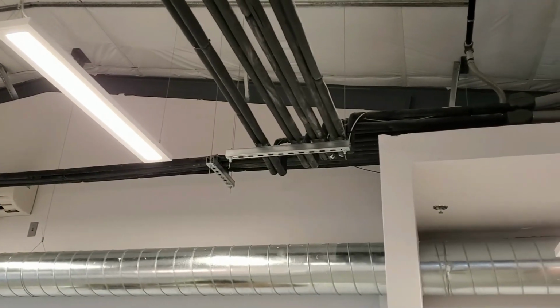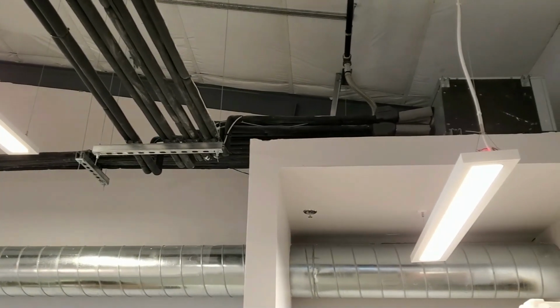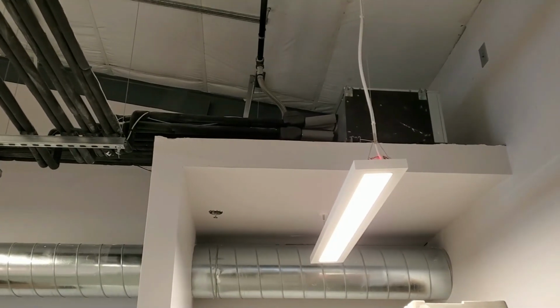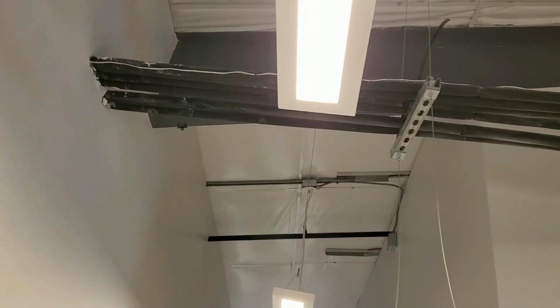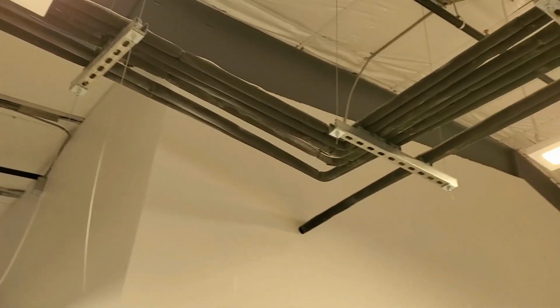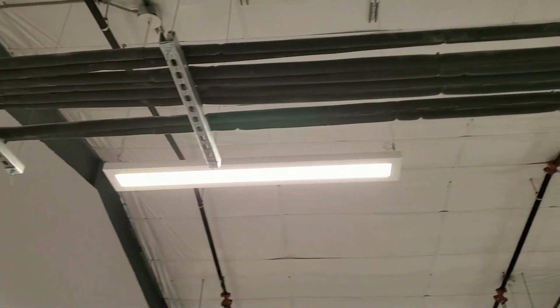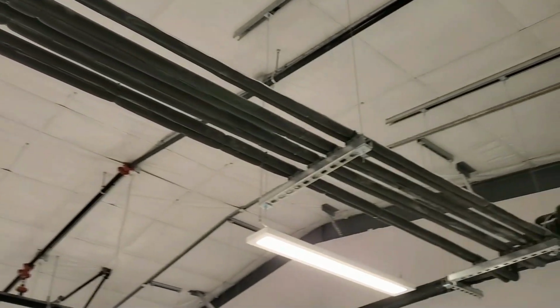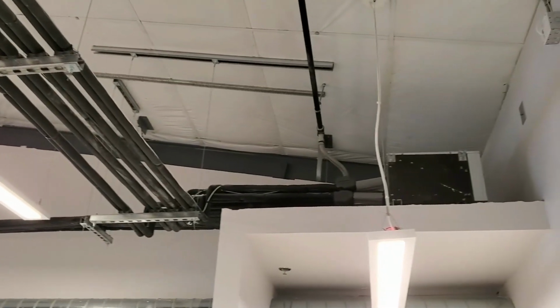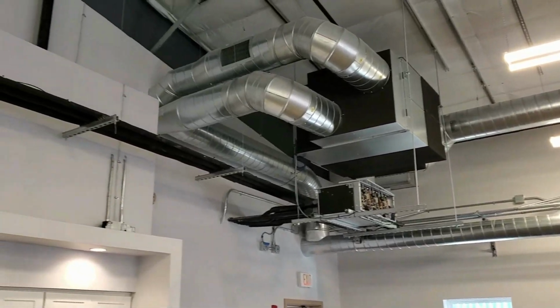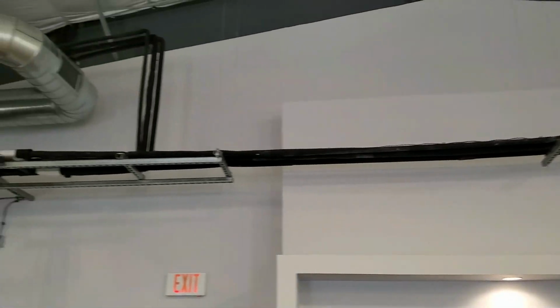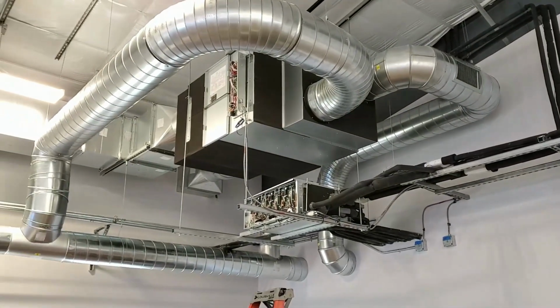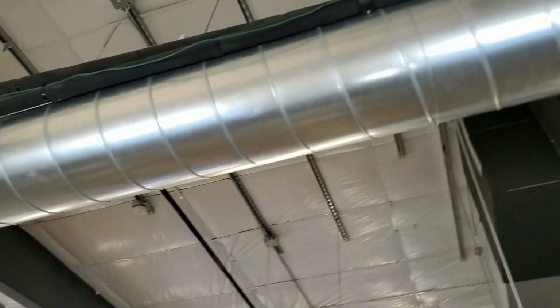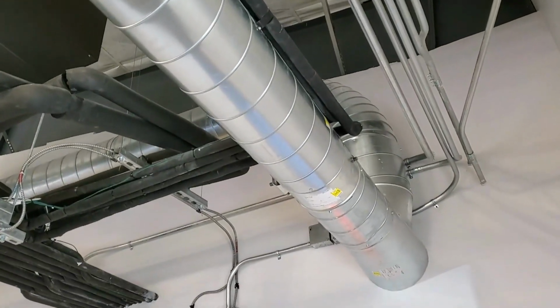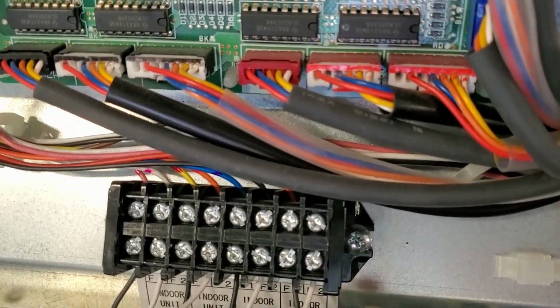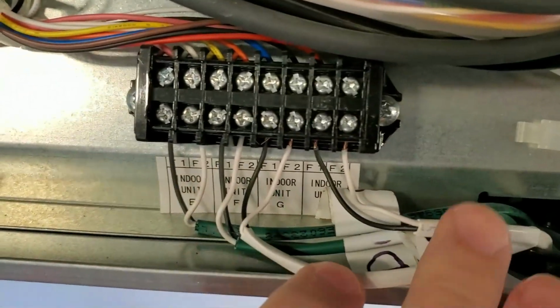So a 3-pipe VRF system where you have branch boxes, branch selector boxes. And I'm going to add one more thing to it. This only applies if you have a branch selector box from a Generation 4, VRV4 product and later. So the newer style PCB. If you have the older VRV3, VRV2 heat recovery systems, this particular step is not going to apply to those branch boxes. This only applies to the Generation 4 and later branch boxes as of the time of this recording in 2022.